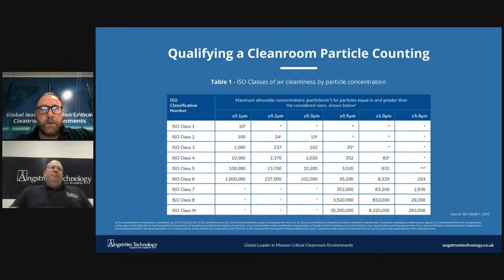After the particle count samples are taken, the engineer will refer to Table 1, ISO class of air cleanliness by particle concentration. This table contains the maximum allowable concentrations of particle sizes by the ISO class. Most engineers have these levels committed to memory, but just in case they don't, it's here to refer to. The engineer will now be able to determine what ISO classification the cleanroom has achieved. For reporting purposes, this will have to include the ISO class, the occupancy state, and the lower and upper considered particle sizes.